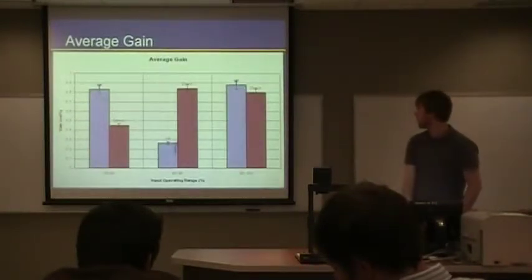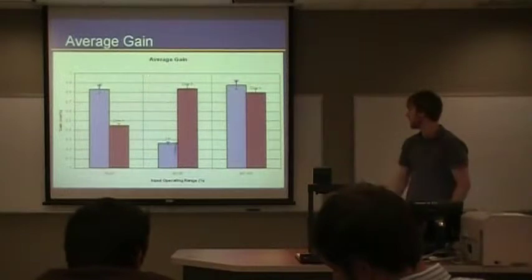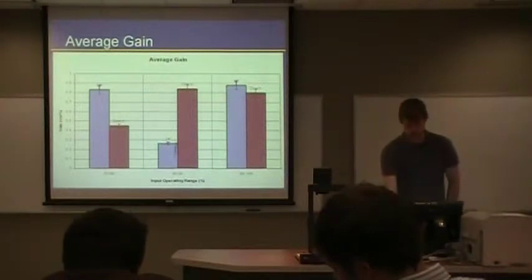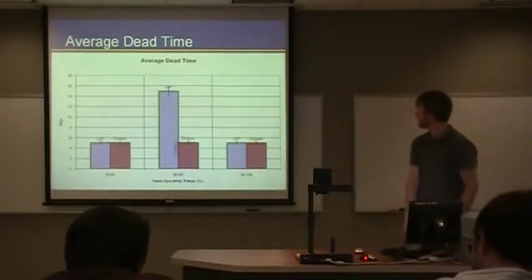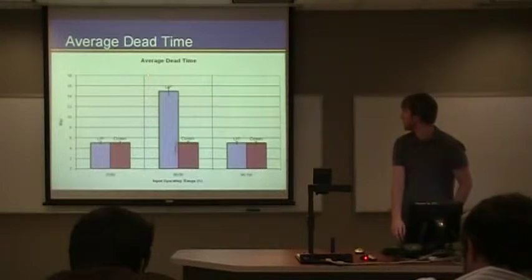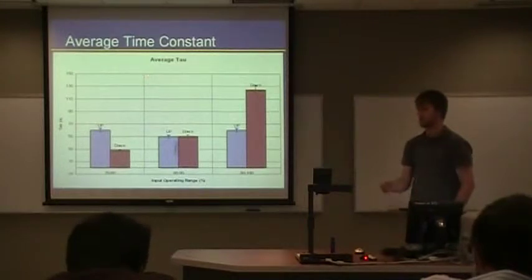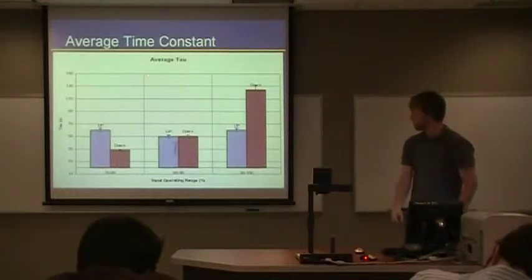The average gain that we received up and down is shown pretty stable across the board. The only two that stand out from the rest are the down from 70-80 and the up from 80-90. And repeatability might level that out if we do more tests. But as such, that's what we have. The average dead time hangs around five seconds, except for the one that you can see sticking up there from 80-90, and that took 15 seconds. The average time constant that we found for our system using the step response, the first order plus dead time model, is shown around a minute. This is the average that we found for all of the steady state range.